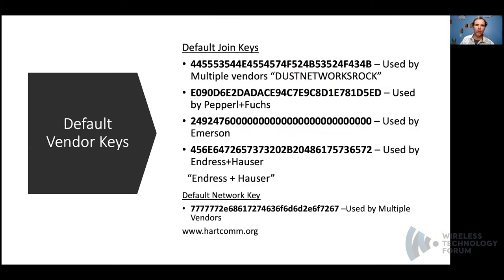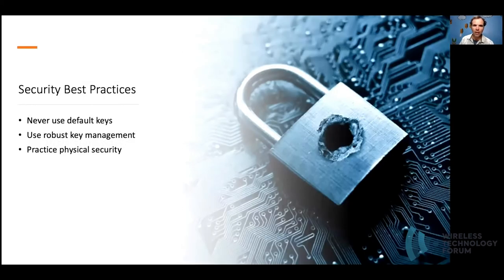Here you can see some of the default join keys used within typical vendor WirelessHART deployments. If you enter these hex values into a hex-to-ASCII decoder, you'll find some interesting Easter eggs — for example, one translates to DUSTNETWORKSROCK, and the last one to Endress and Hauser. You also see some default network keys as defined by the HART standard. It's important to remember that wireless communication will always be vulnerable to jamming attacks. There are many countermeasures built within WirelessHART, but any wideband jamming can only be resolved by identifying the source of the interfering signal and physically powering it down.